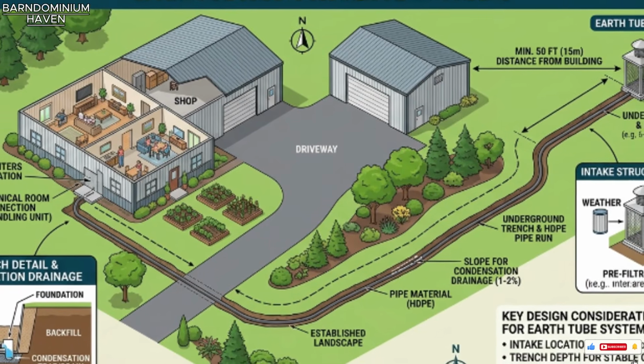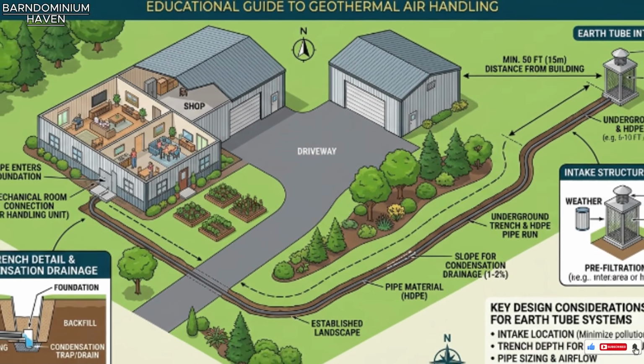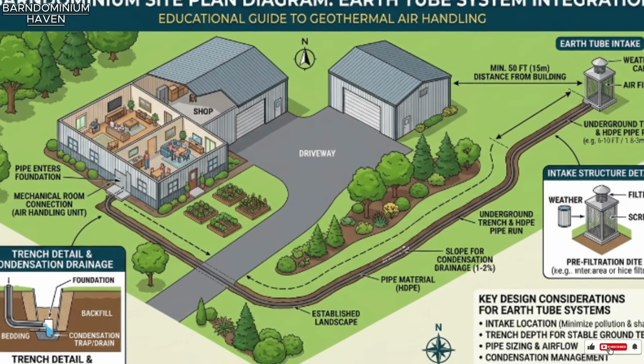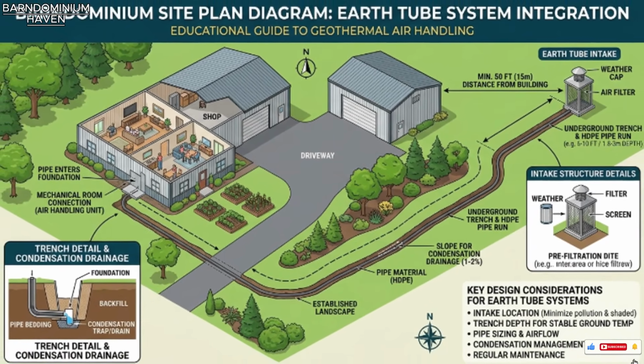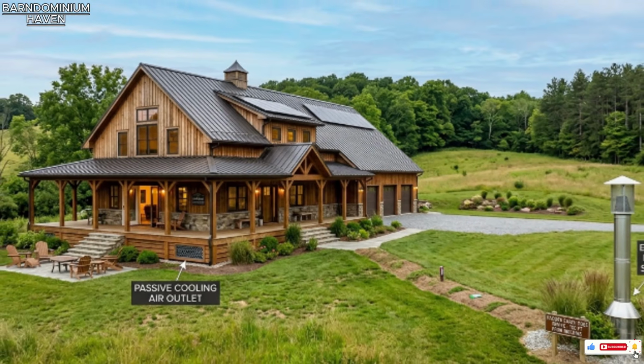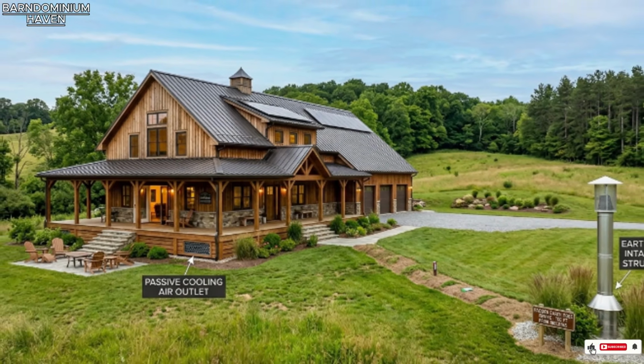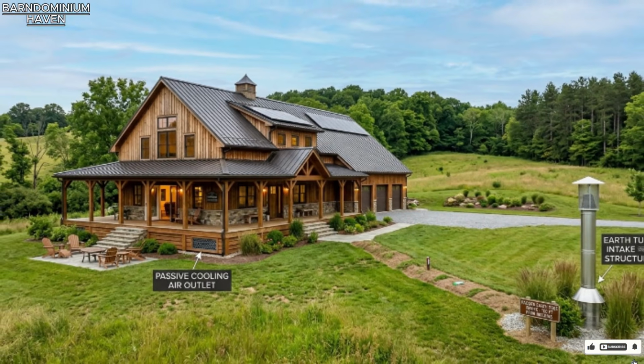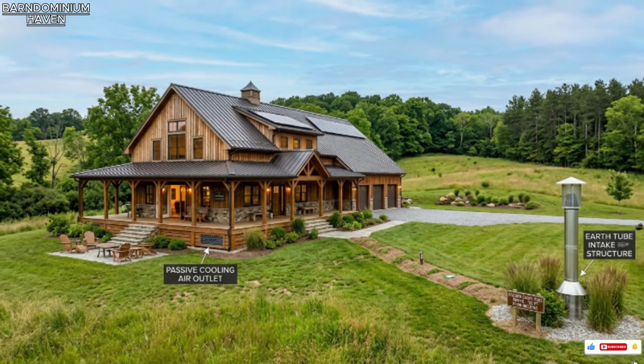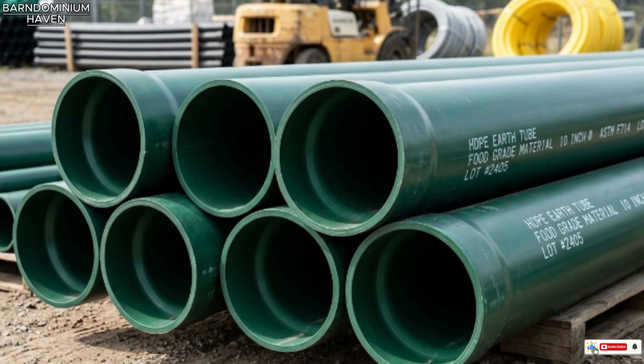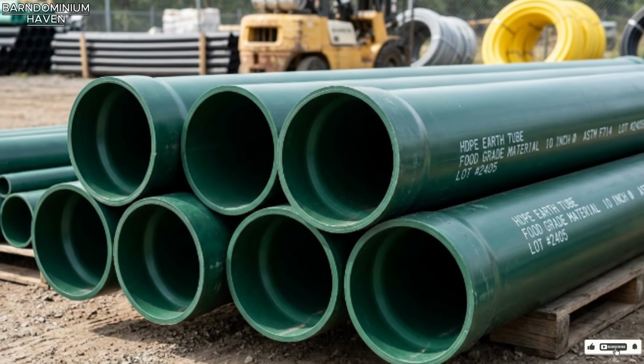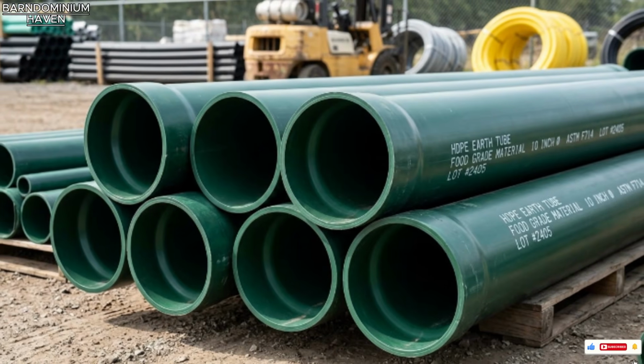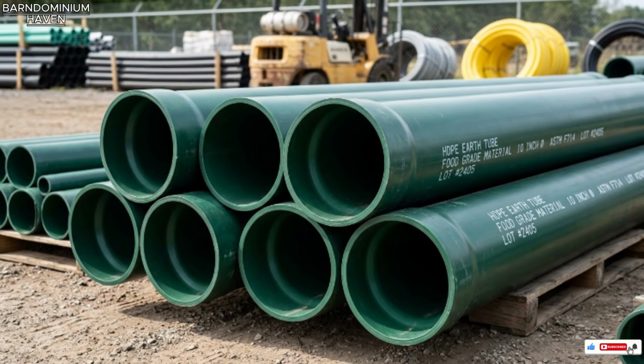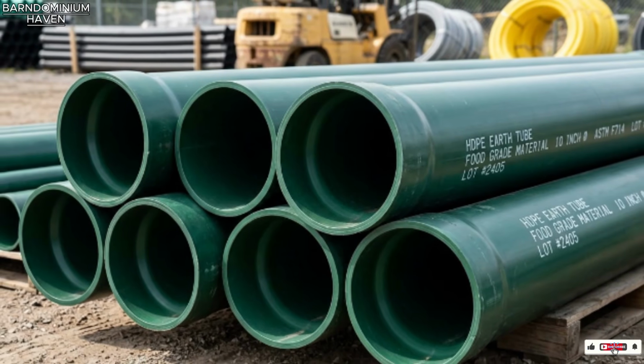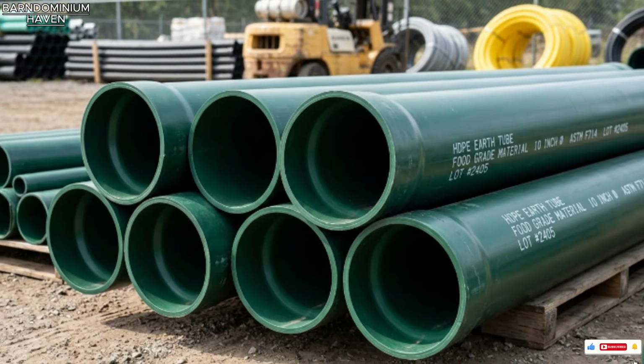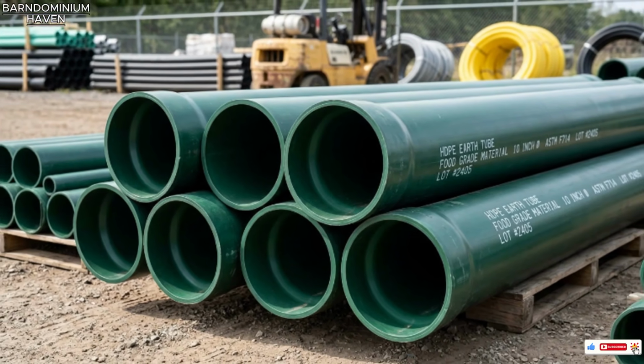Let's talk about what an earth tube system actually costs to install in 2026. Because the operating cost of $5 per month is the number that captures attention. And the installation cost is the number that determines whether the system makes financial sense for your specific build. Earth tube pipe, 8 to 12 inch diameter smoothbore HDPE pipe, food grade or ASTM rated for underground application, 100 to 200 foot run, $800 to $2,400 for materials alone.